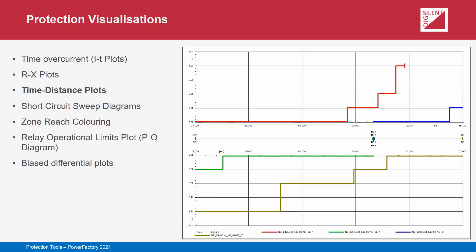Time-distance plots are often associated with distance protection, providing a good visualization of the reach of each zone of each relay in relation to its neighboring devices. They can also be used to visualize overcurrent protection performance. The plots illustrate the variation in relay device operating time as faults are applied at intervals along a specified path. The user can choose the nature of the short circuit — three-phase, line-to-line, or line-to-ground faults — as well as the short circuit calculation methodology, for example the complete method, IEC 60909, or ANSI.